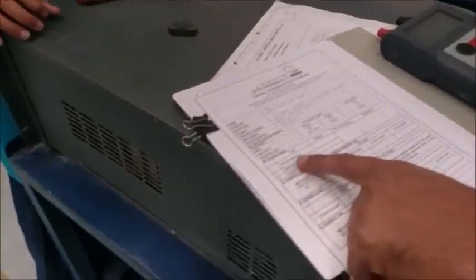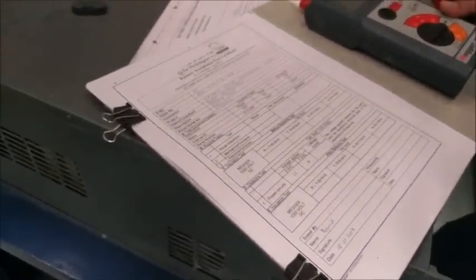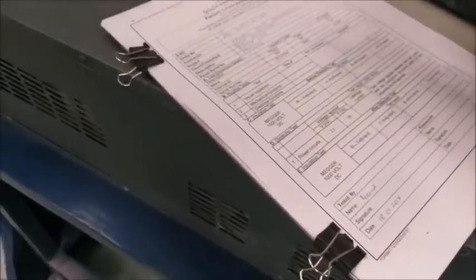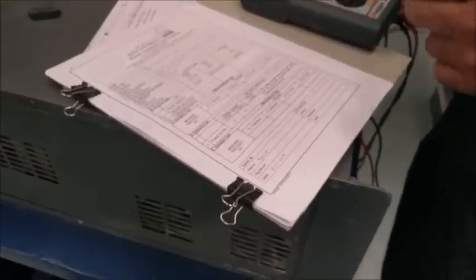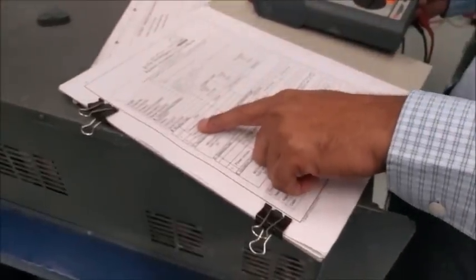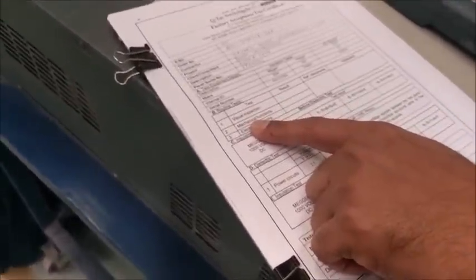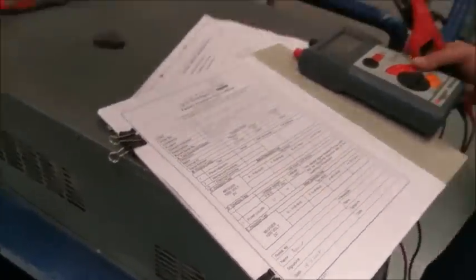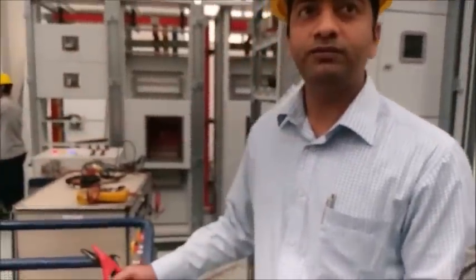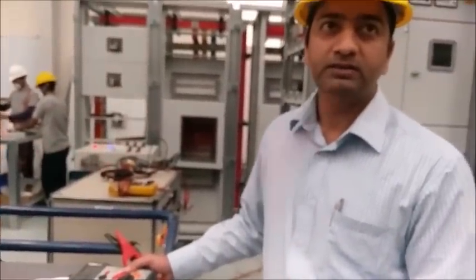Now for visual inspection, we have two things. One is the bill of material verification, whatever we have as per the drawing, is it installed in the panel or not. The second thing is the dimensions, as per the manufacturer. So as-built drawings and approved drawings, we have two things in visual inspection. In mechanical functions, we have to see that the ACB, MCCB, each and every function of the breaker is satisfactorily working or not.